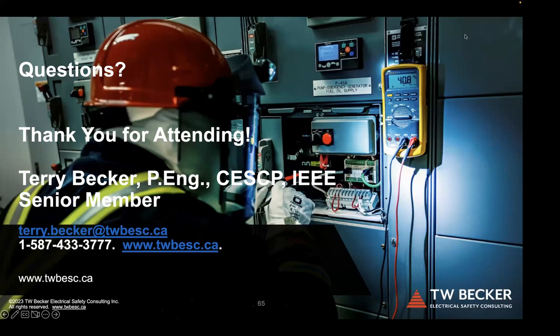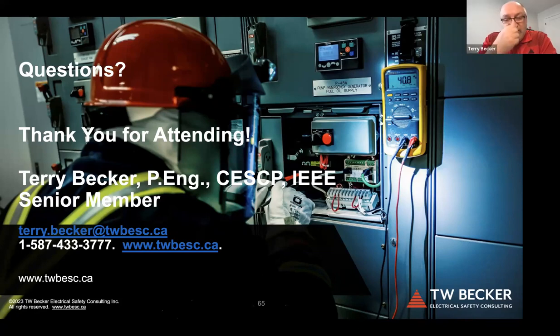Okay, thank you so much, Terry. So the next question I have: do rubber insulating gloves require testing? I mentioned that we need dielectric testing of shock PPE, and these rubber insulating gloves need to be tested and have a test date on them that would indicate within the last six months. It's the American Society for Testing and Materials standards that indicate we need these gloves dielectric tested every six months. And what happens is, I'm out on a site and I look at the gloves and they're not tested every six months. You've got to set up a PM and regularly get these out to an approved lab that can do the tests to meet ASTM requirements.